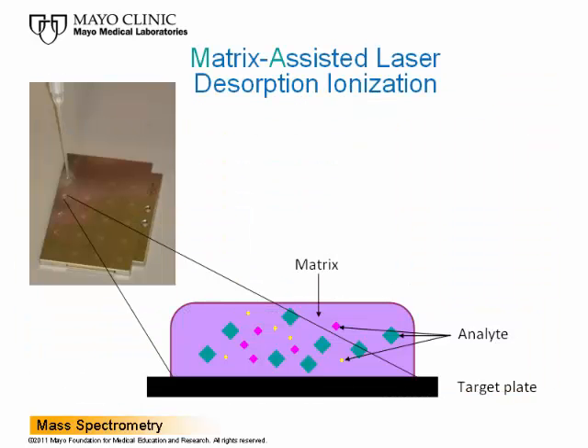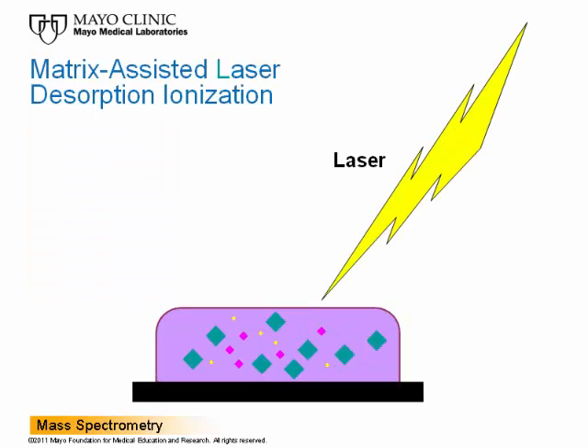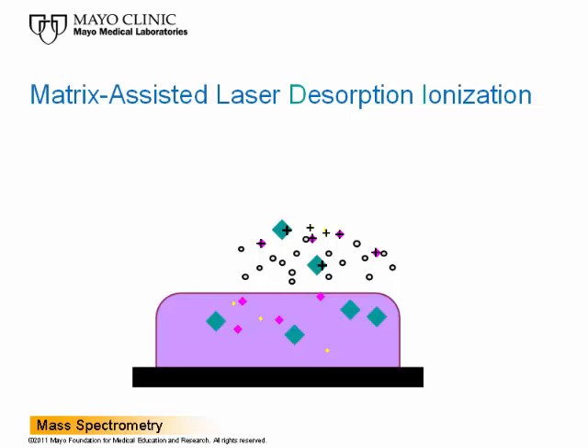The sample is mixed with the matrix and co-crystallized onto the target plate — the matrix-assisted component of matrix-assisted laser desorption ionization. The matrix buffers the sample, preventing its decomposition and enabling transformation of laser light into heat. A laser is applied — the laser component of matrix-assisted laser desorption ionization. The matrix absorbs energy from the laser, releasing it into the sample as heat. This causes the sample to desorb and form singly charged ions — the desorption and ionization component of matrix-assisted laser desorption ionization.